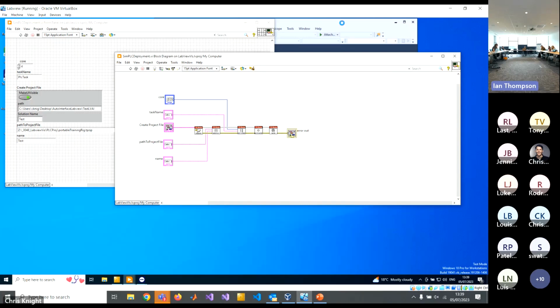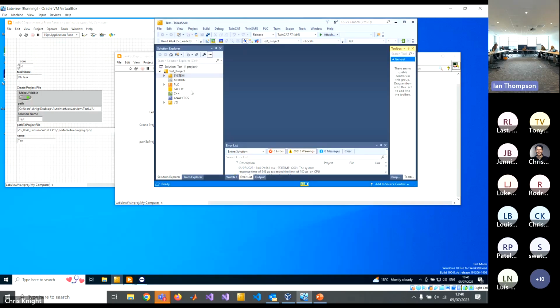But yes, the real reason we did it originally was to handle machine variations. So you have a machine that has 6 components, say, but the machine builder can deliver that in 1 or all 6 versions of it. That becomes a pain in the backside to do on a production line. So they basically saved an IO configuration for each variant and went, we'll load that one in. And that comes back to the GUI I was talking about with the machine operator, where they pick that one. So you can literally create everything from scratch, or you can save it as templates.